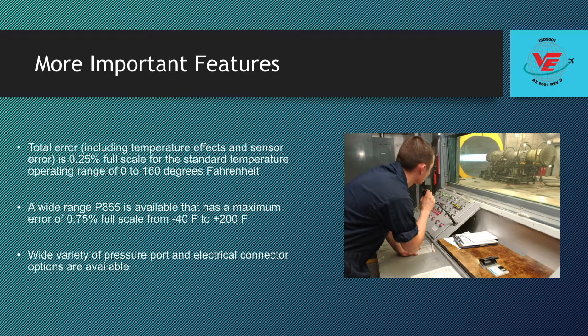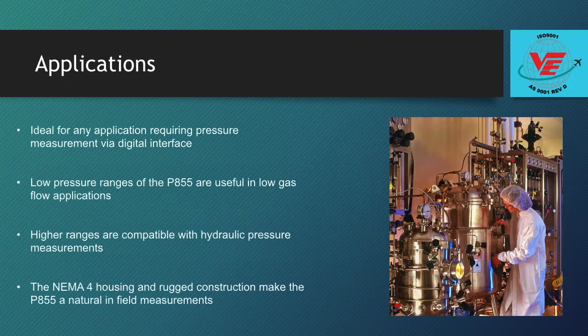All P855s are characterized for output shifts over the operating temperature range, and the output readings are corrected accordingly. The result is that the total error, including temperature effects and sensor error, is just 0.25% full scale for the standard temperature operating range of 0 to 160 degrees Fahrenheit. A wide-range P855 is available that has a maximum error of 0.75% full scale from negative 40 degrees Fahrenheit to positive 200 degrees Fahrenheit. The P855 is ideal for any application requiring pressure measurement via digital interface.